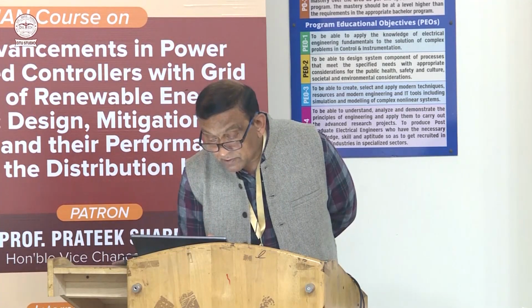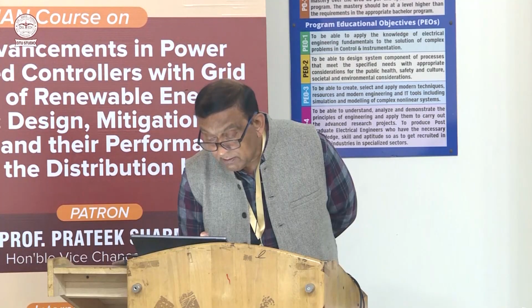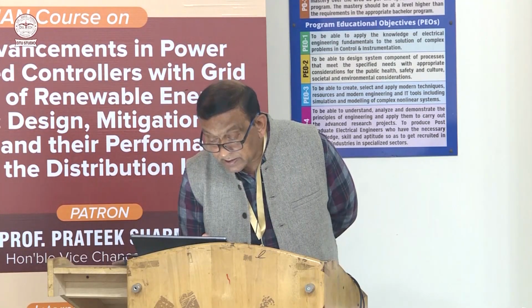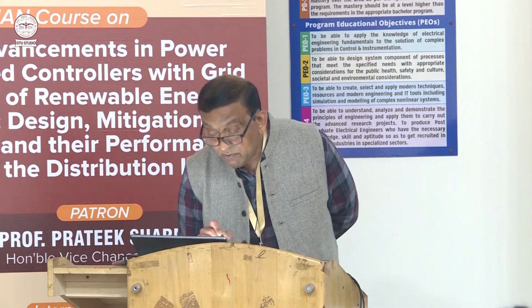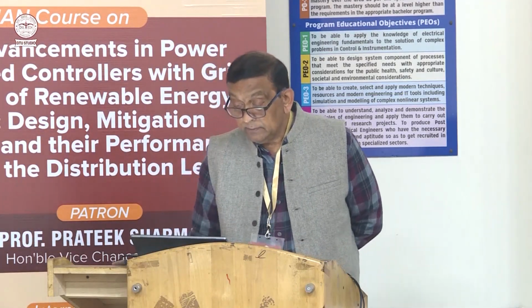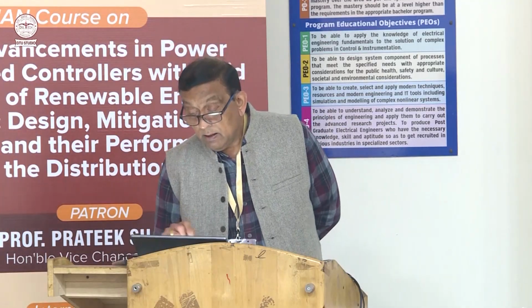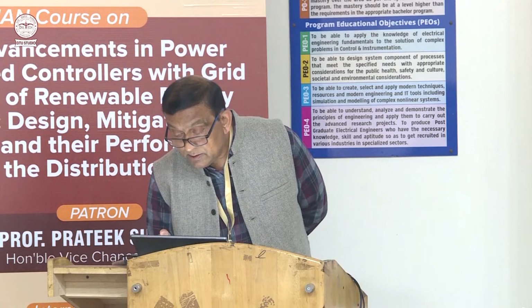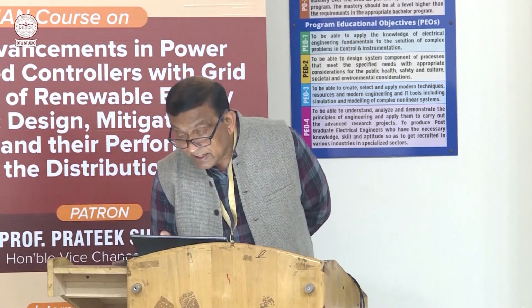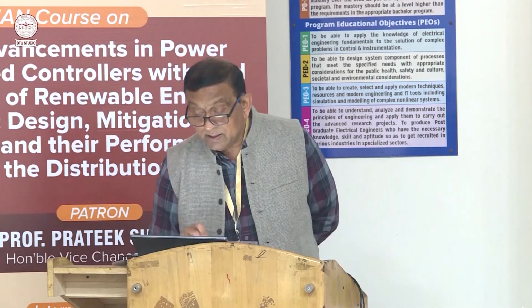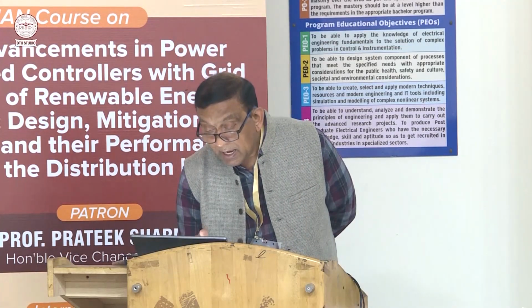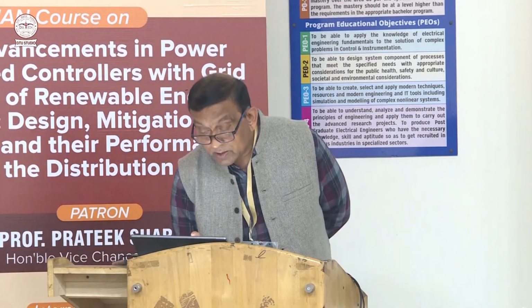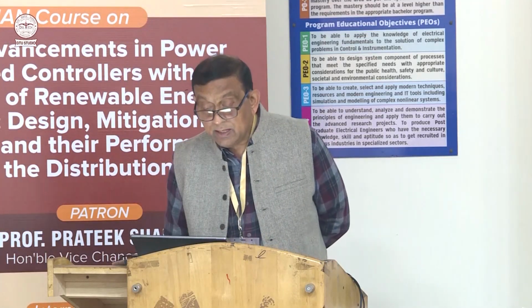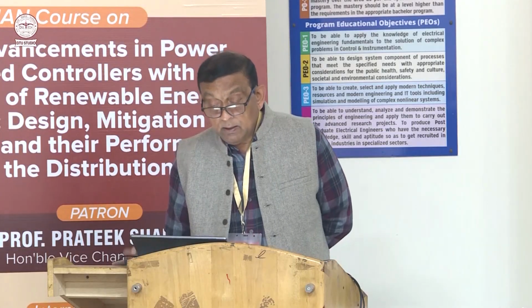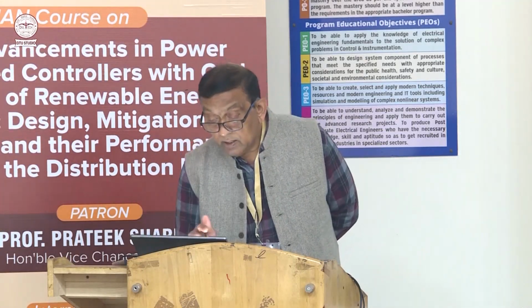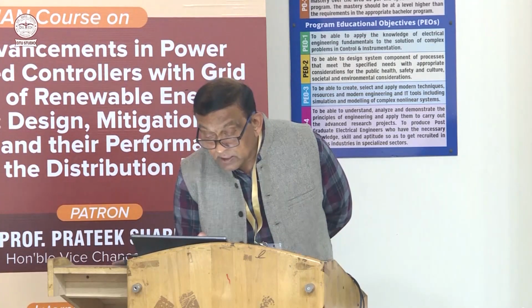And then we have, if the size of the system is increased, we can go to 7%, for larger size 10%, and if the size is more, then we can go to 15% individual harmonic, while the total, you see, is still for a smaller system 5%, and then for a larger system this limit is increasing. As far as higher harmonics are concerned, if harmonics are between the 11th and 17th harmonic, like 11th, 13th or 15th, those harmonics, the limit, you see, is reduced.